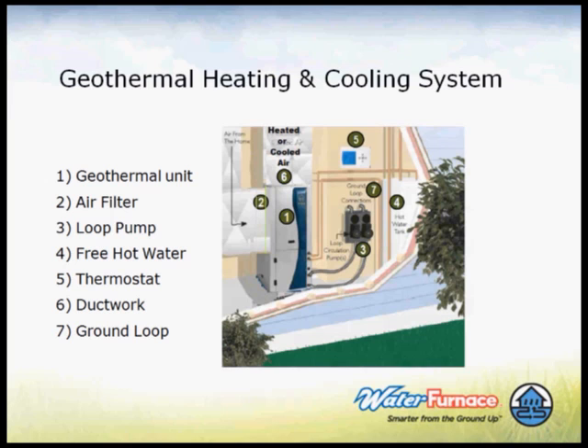We offer variable speed pumps, but in most applications they're not really necessary. However, our new 7 series unit, which is now 2 years old, has a variable capacity compressor, and we do recommend a variable flow pumping system for that. Otherwise, if you're using open water, you just regulate the flow with an orifice that controls the amount of water flowing through. So variable pumps are available, and there's probably a little bit of benefit even on a standard system. Not sure if that would offset the cost, but they're available.